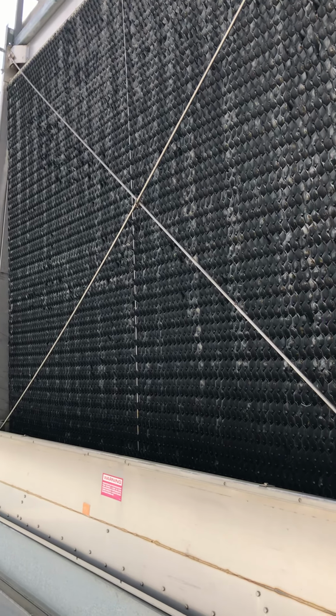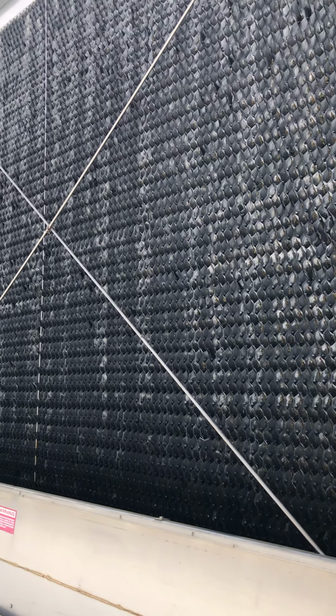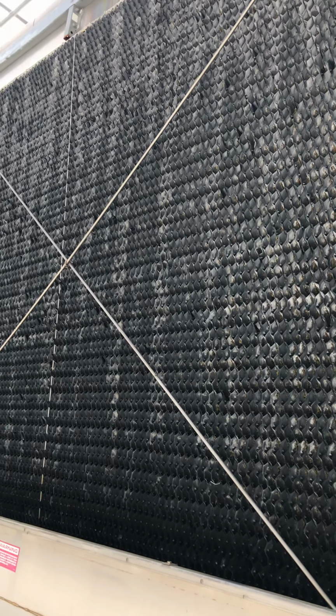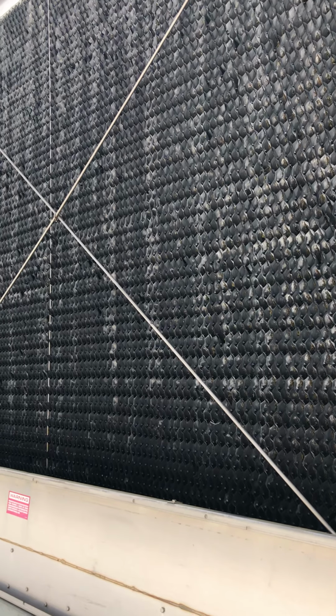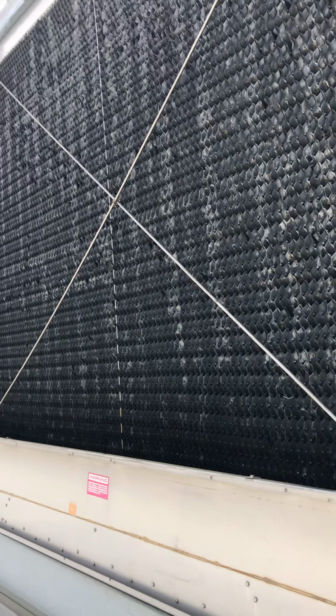If we let the scale build up and build up, what do you think would happen? We wouldn't have heat transfer, exactly. And then we would have the deterioration of the fill. These things are about 12 inches thick, if I remember right. Some of them vary. And you have to do a refill on your fill. So again, maintenance is crucial when you start dealing with anything with water, especially cooling towers. It's something you've got to stay on top of.